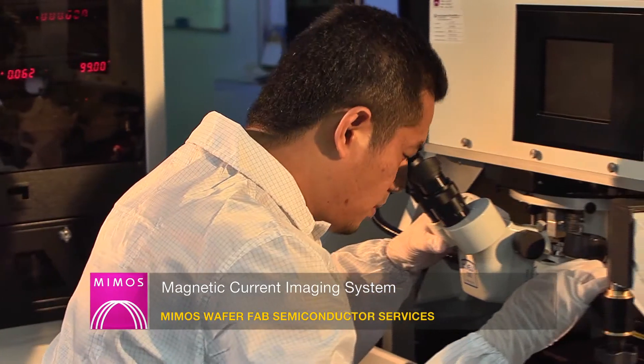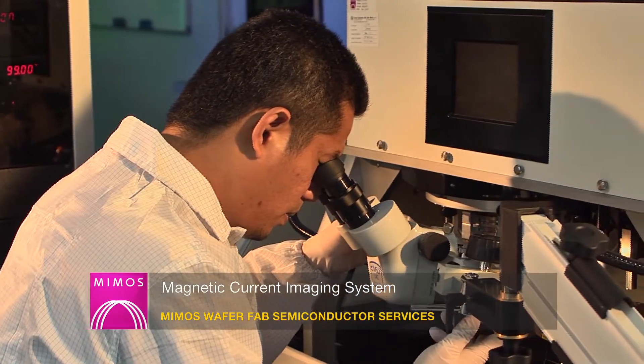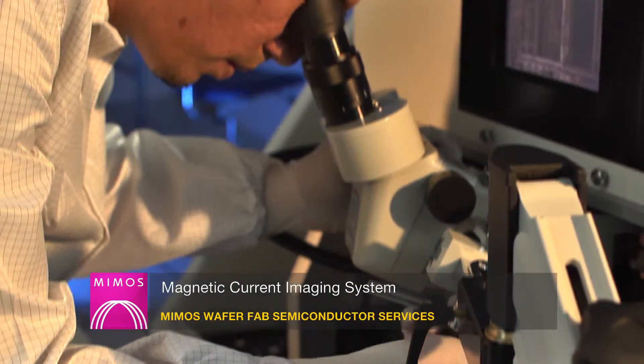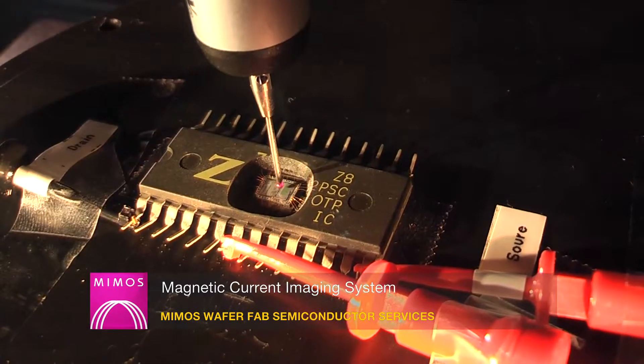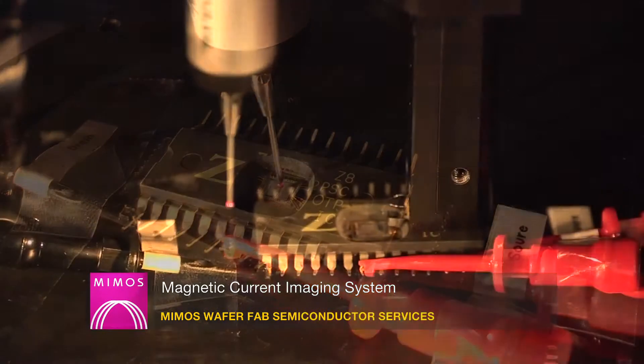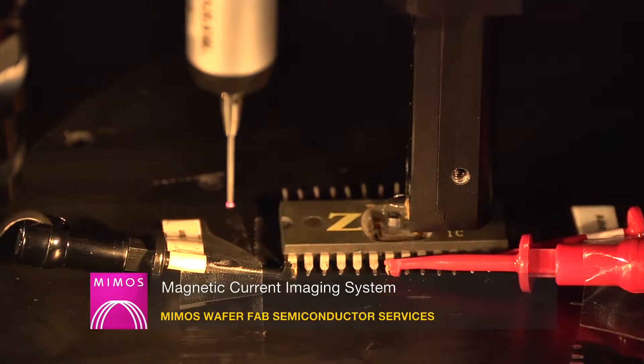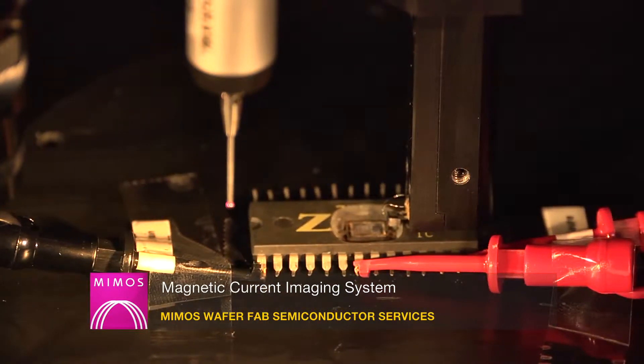Magnetic current imaging system is used to localize semiconductor failures through the measurement of weak magnetic fields. By mapping out the current flow in an IC or package, all types of short and conductive paths can be localized.